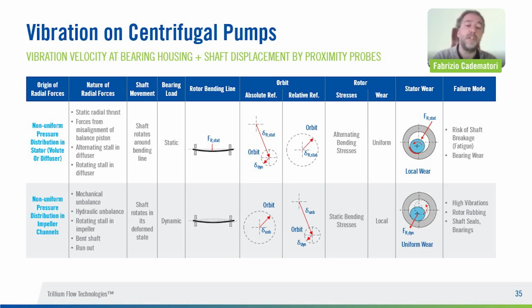For the first condition, rotor dynamic is probably okay, but for example, the resonance of the bearing is possible, while for the second case, shaft rotor dynamic is problematic. A non-uniform pressure distribution in the stator causes a static bending line of the shaft, with alternating stresses and risk of shaft breakage due to fatigue.